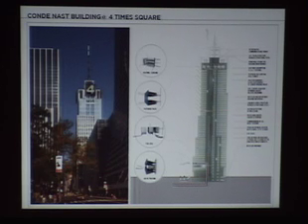So we've gone well beyond this technology, but there's still a number of things that we actually have not repeated in an office building. One is the fuel cells. Unlike almost anything else in the green business, the cost of fuel cells went up rather than down. Those technologies are being advanced to the point where now we have hopes that it's going to become feasible. The problem is that although it's very clean because you're producing energy on site, it's about 85% efficient as opposed to 50% from the grid. It requires maintenance every 5 years, which is replacing the major parts, and I'm not sure exactly what its payback is now, but we estimated about 10 or 12 years when we put these in.